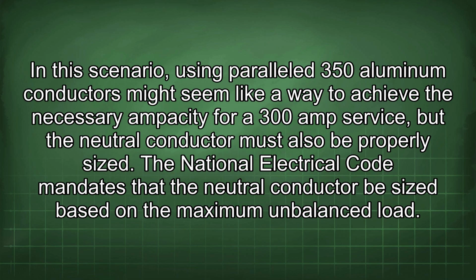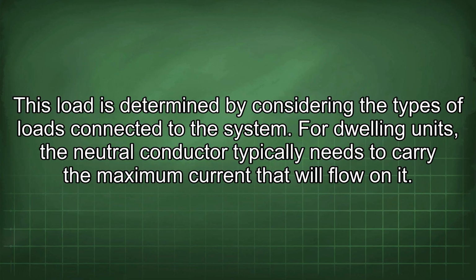In this scenario, using parallel 350 aluminum conductors might seem like a way to achieve the necessary ampacity for a 300 amp service, but the neutral conductor must also be properly sized. The National Electrical Code mandates that the neutral conductor be sized based on the maximum unbalanced load. This load is determined by considering the types of loads connected to the system. For dwelling units, the neutral conductor typically needs to carry the maximum current that will flow on it.